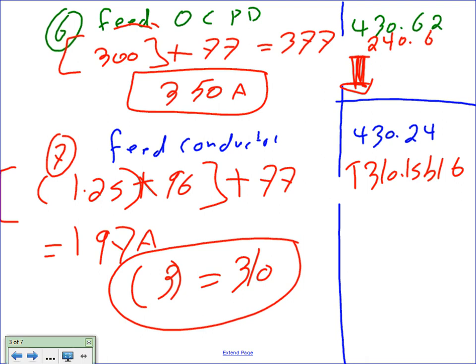But if it's just a feeder tap like we did, guys, and I know I'm not going to add to this feeder in the future, it's a good idea to size it based on the code minimum. Everything that we did, guys, in terms of conductor is minimum, in terms of overcurrent protection device is maximum.